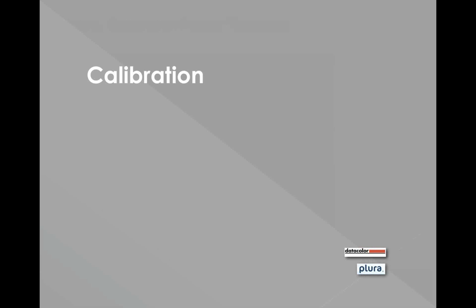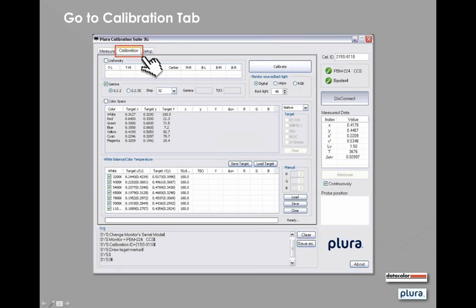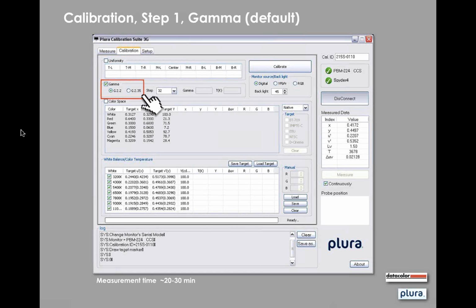So we'll move on to calibration, and again, this is going to look like a lot of information, but really we just have to go to the important bits and make sure we pay attention to those. So we click on the Calibration tab, and you can see there's a lot of information on the screen. It's organized into segments, and we're going to address some of those. The first one we're going to do is set the target gamma. Now, most people are going to go to gamma 2.2. That is the default, and that's also the default for computer-based calibration, so it's easy to remember.